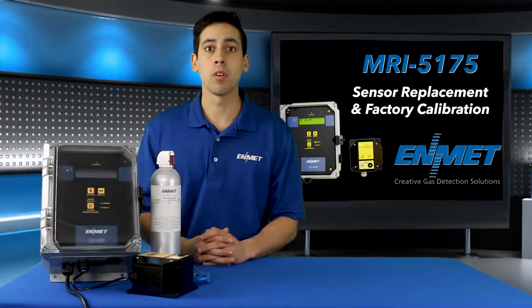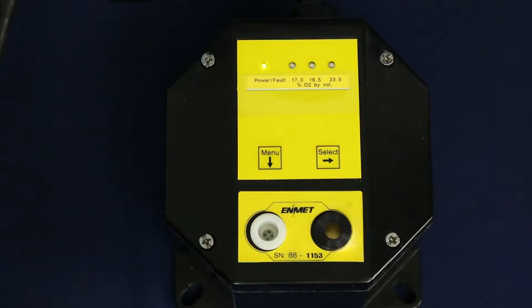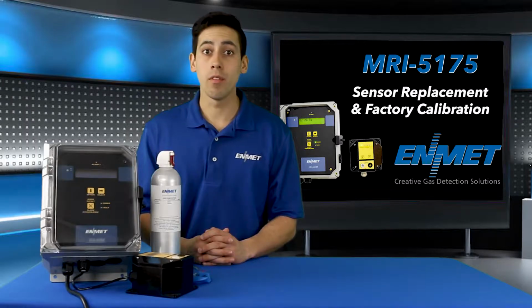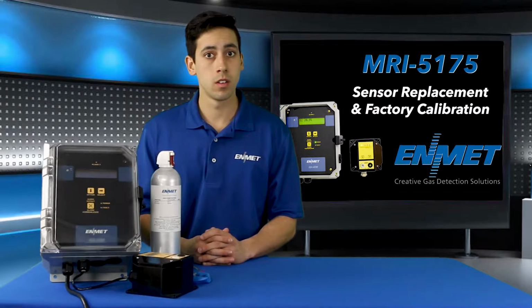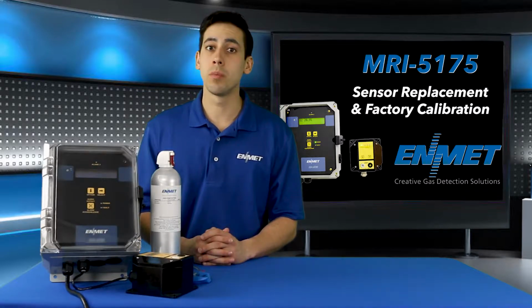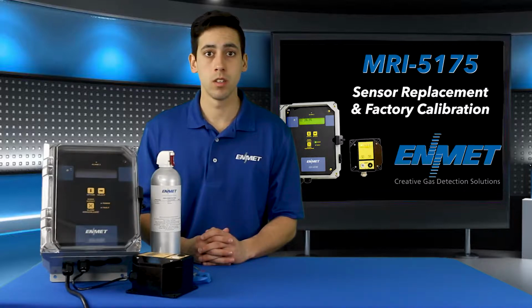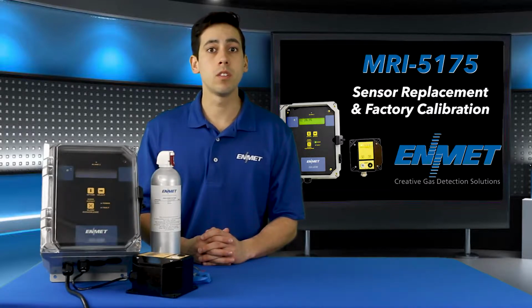Once the sensor is replaced and the cover is properly reinstalled, power up the unit. You must wait 3 to 4 hours to recalibrate the sensor. However, an overnight stabilization period is preferred. Following a sensor replacement, you must perform a factory calibration. The MRI 5175 calibration is a 1-point calibration. There is no zeroing step required.